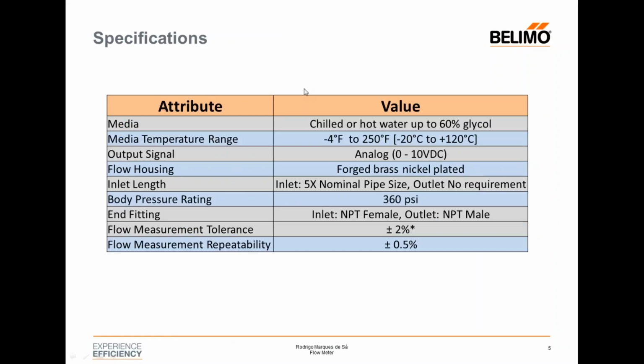Here are some specifications. For the media, we're able to measure and read chilled water, hot water, and up to 60% glycol. For other media, like open loops or steam, we are not able to read that with these flow meters.